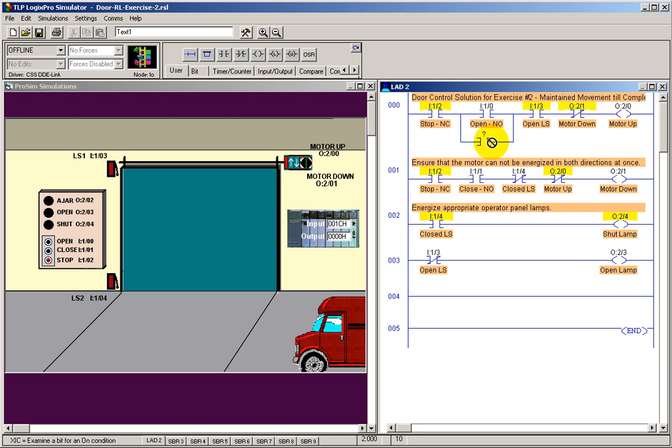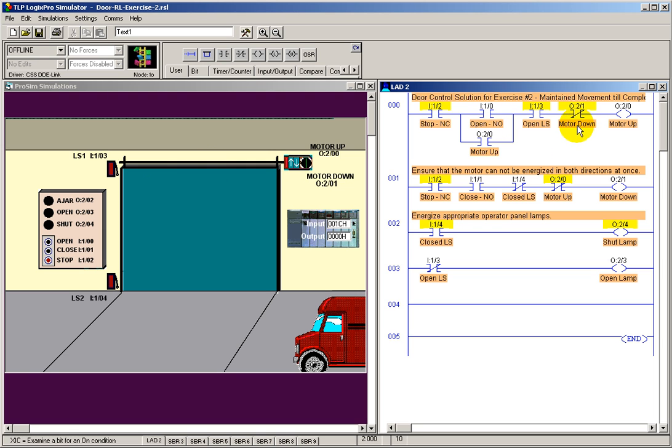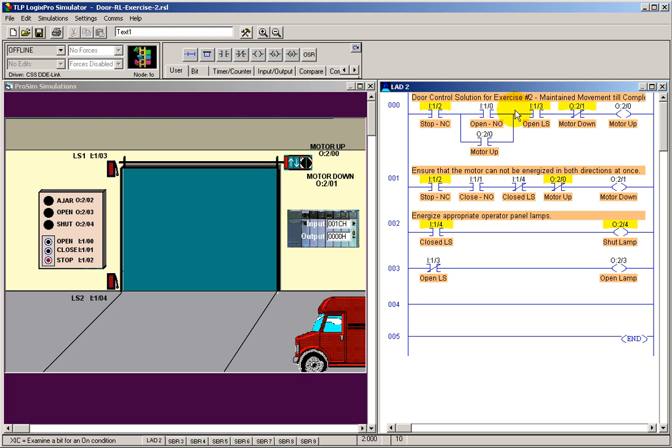Let's drag this guy over to here. Now, when this is initially sealed in, this is a momentary switch. This condition is true. This condition will be true. The open limit switch will have to be activated, which means it's anything but fully open. And we'll make sure that the motor down isn't running. That's this output. And then we'll activate our motor up. But the second somebody releases it, this guy is going to actually take over and create this parallel path of logical true to get to this motor up.